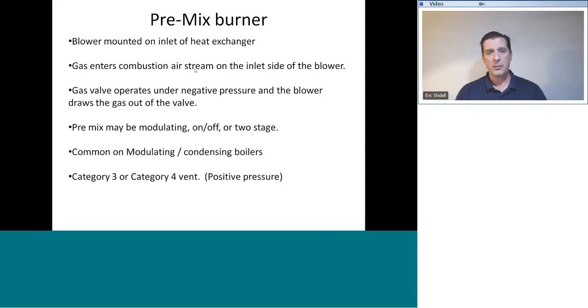These are very common on modulating and condensing boilers, and they may be either a category 3 or a category 4 certified appliance. Category 4, as we said, is a positive pressure vent condensing low temperature flue products. Category 3, we haven't talked about yet. Category 3 is a relatively rare bird. That means that it is a positive pressure vent, but it is non-condensing, high temperature, such as those bigger boilers that I just mentioned are often category 3 appliances.